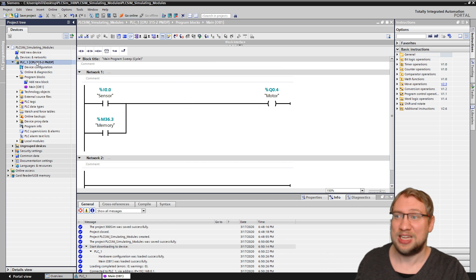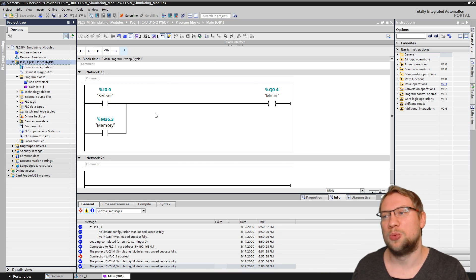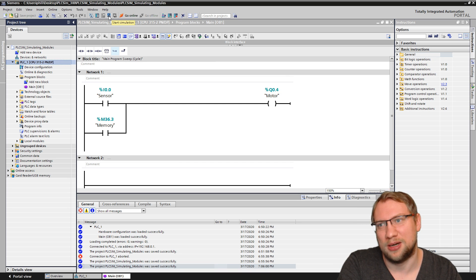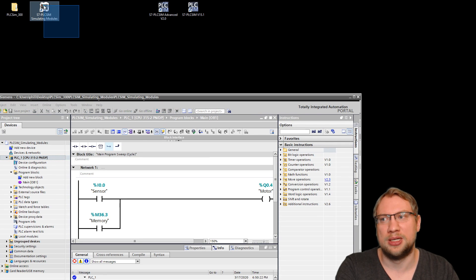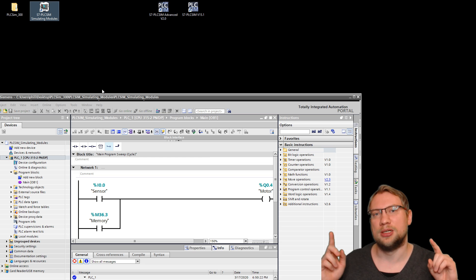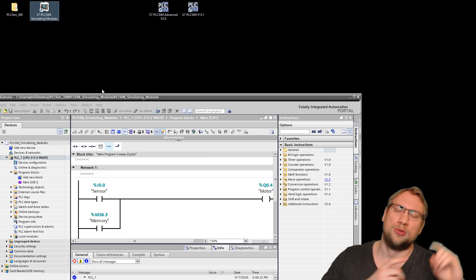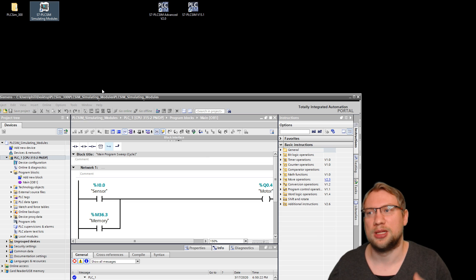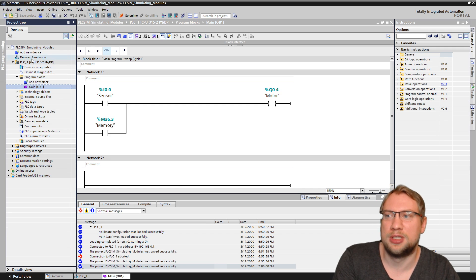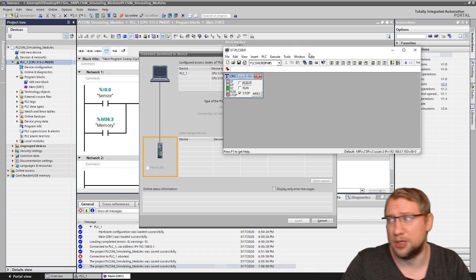Now I would normally test this by downloading it to the machine using the download to device button, but I don't have a device here. So what we need to do is simulate. Right next to the upload button, we have a Start Simulation button. If I press this button, a different software opens — that's our S7 PLC-SIM Simulating Modules. It usually installs directly when you install TIA Portal, but I also have a download link in the description below. If you don't have it installed, check the description — you'll need to make an account on the Siemens website to download it. I have it installed, so I can simply press the button. Make sure you have the PLC selected on the left side, because that's what we want to simulate.